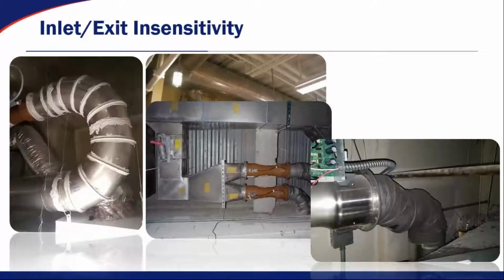And then who hasn't seen a scenario where the pipe fitters come in, put all the water pipes in the building, and then it's up to the sheet metal contractor to make sure that the valve connects up to either a diffuser in the ceiling or to a fume hood in the room. And sometimes you have these crazy snake bends in the ceiling. So we've all seen these type of installations before. And again, none of these affect how the Phoenix controls valve work because we have pressure independence mechanically, and based on Bernoulli's principle, the way the airflow goes through the valve, it is unaffected by elbows inside of a building.